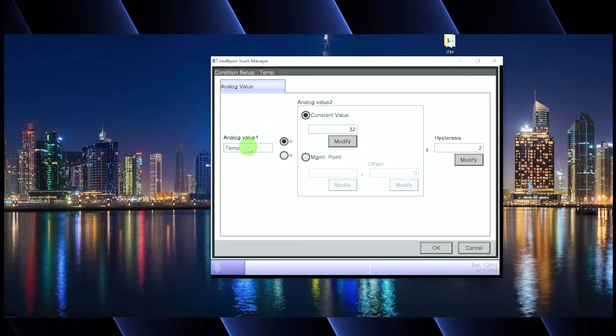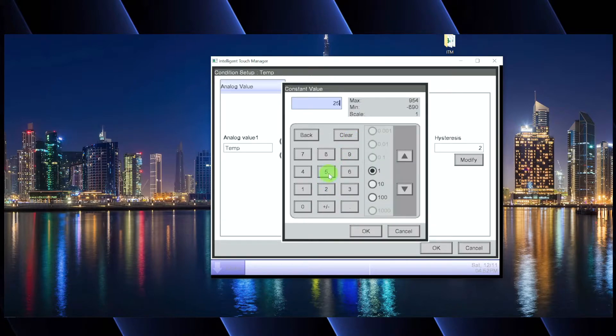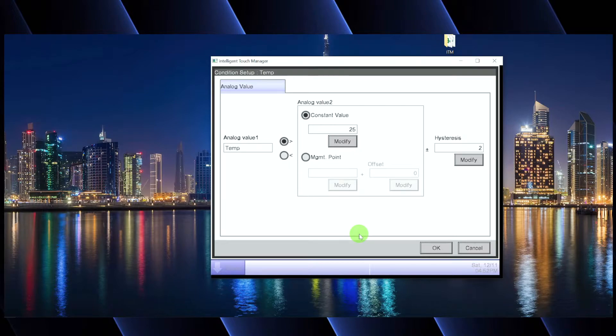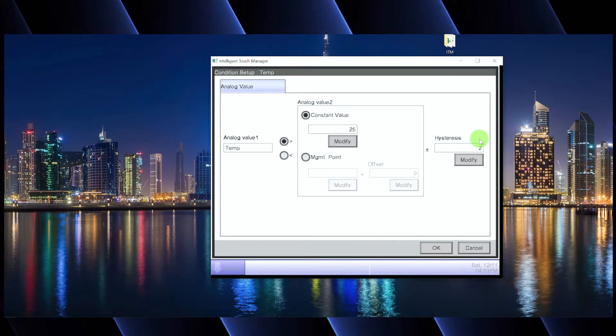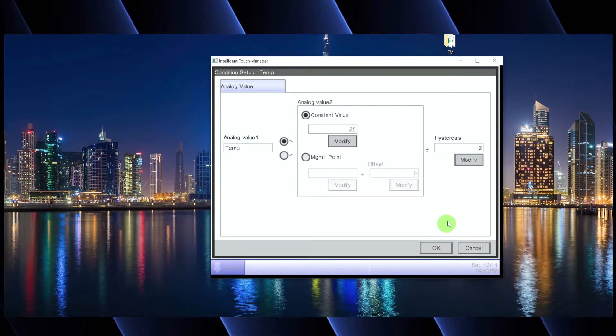We're going to say: if the temperature of this analog value gets above 25 — and since we don't have anything hooked up it just reads 32 as a default — we're forcing the interlock to happen by arbitrarily setting this value. In the real world we'd probably say if it gets above 80 or something like that. Then you have to program in a hysteresis, which is your threshold or dead band. So it would have to get above 25 plus 2, meaning above 27, to enable the condition, and then fall below 25 minus 2 — so below 23 — before the condition is cleared.